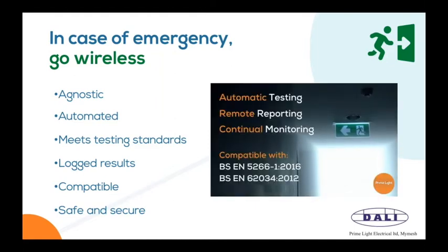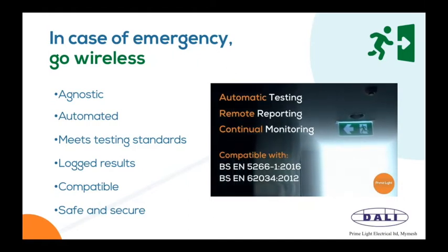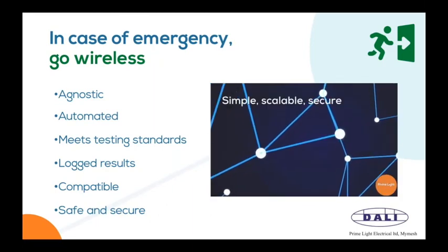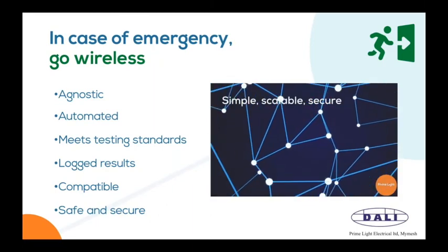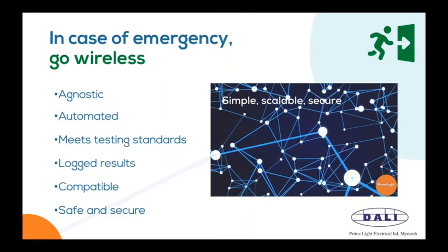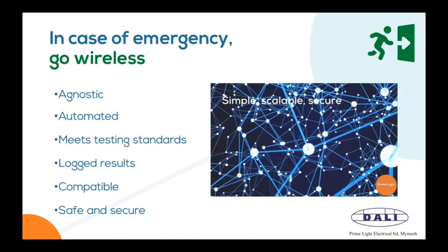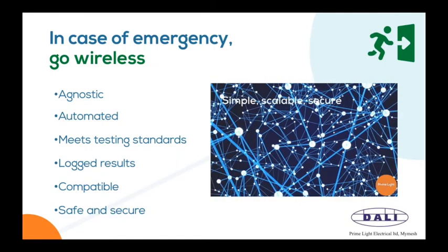The solution is fully automated - install it, the system will test itself and report back to you, producing reports with all the information you need, without someone physically walking around and manually flicking the lights on, which in big buildings is quite a large expense. It meets all testing standards with a full set of logged results for the customer, and it's compatible with any DALI self-testing luminaire, fully safe and secure.